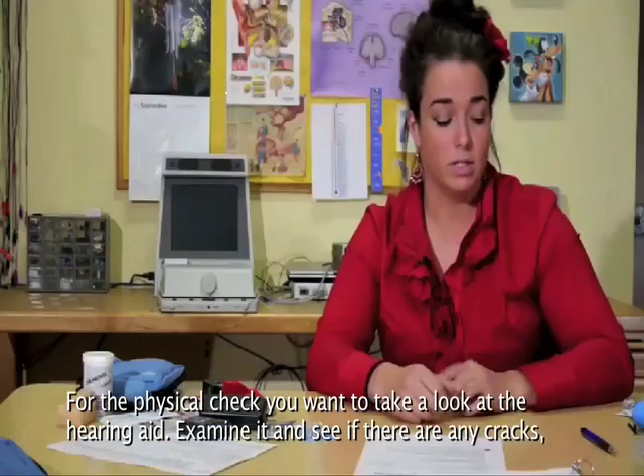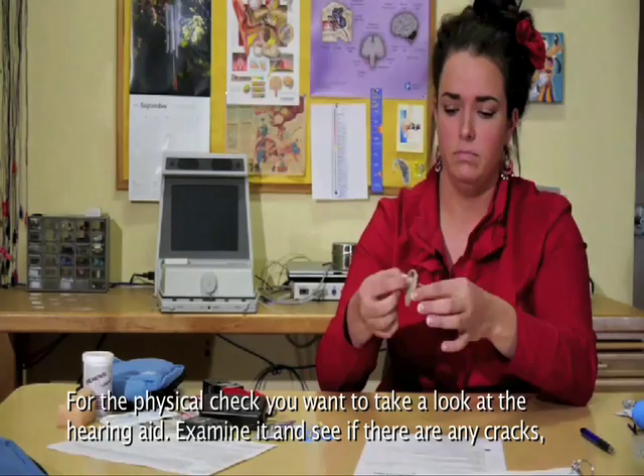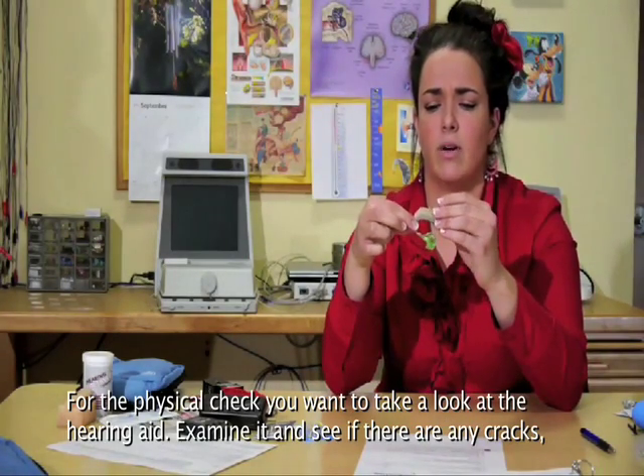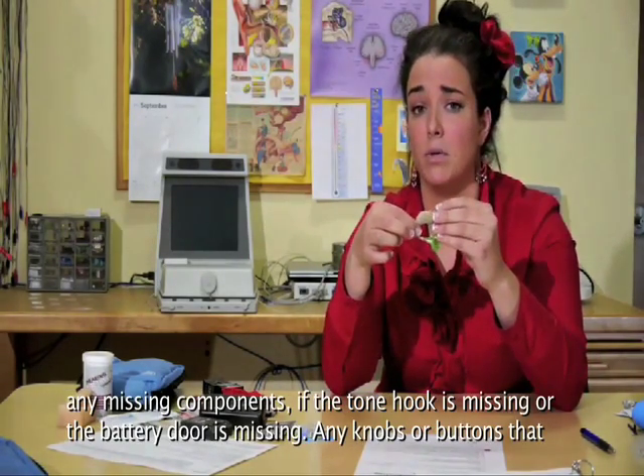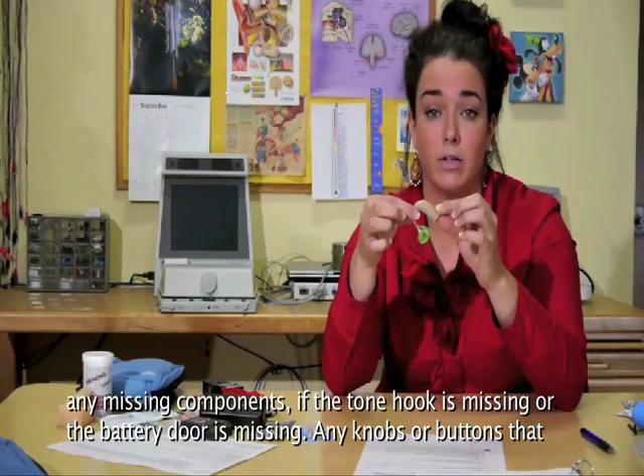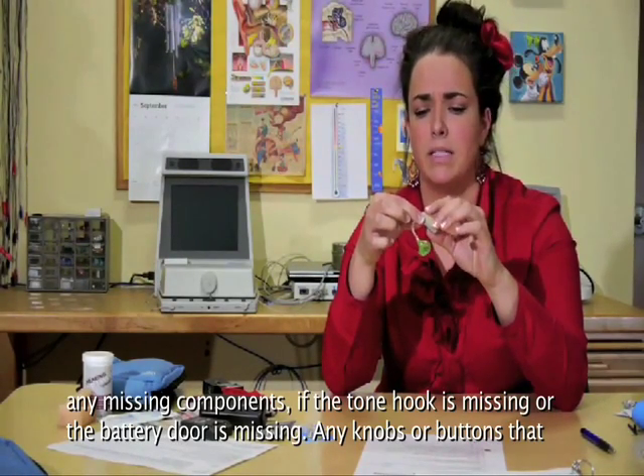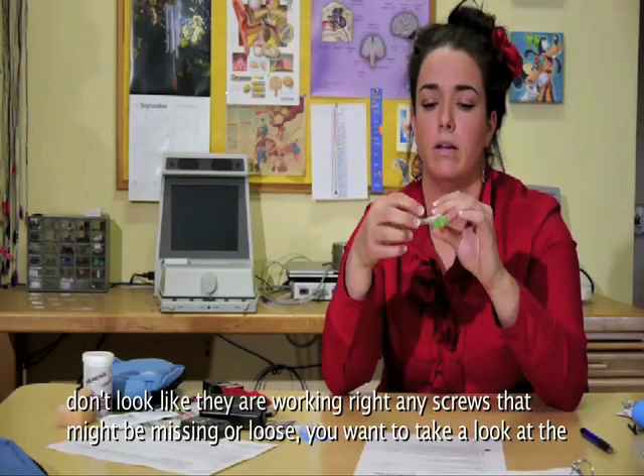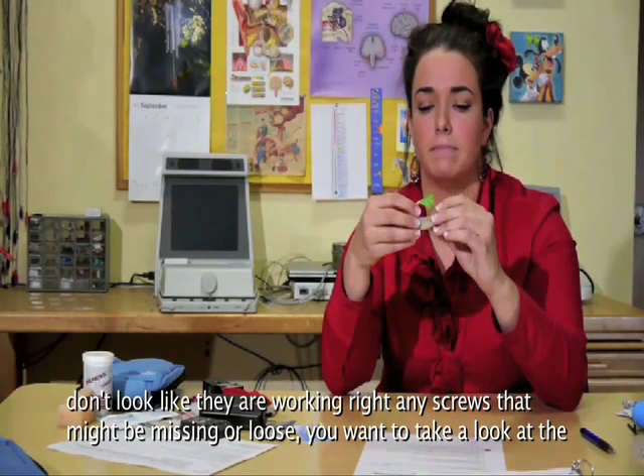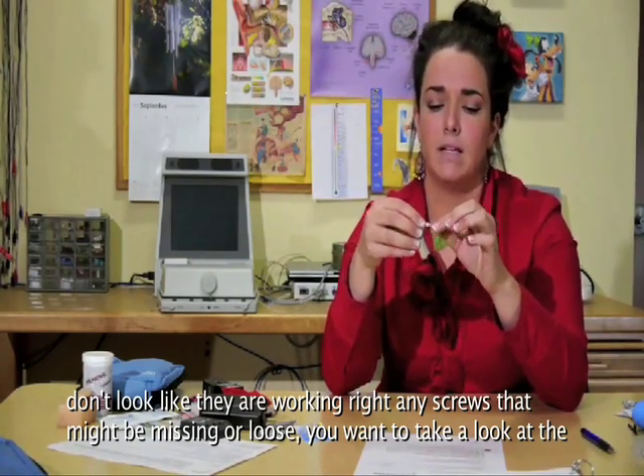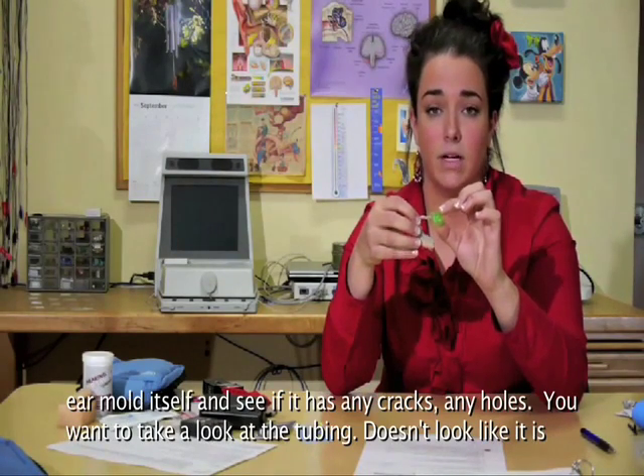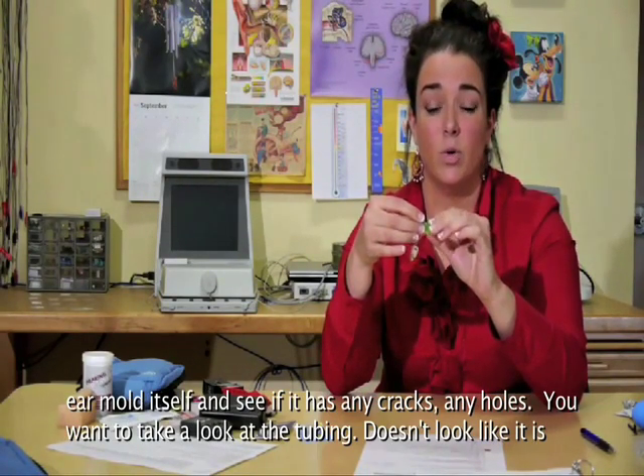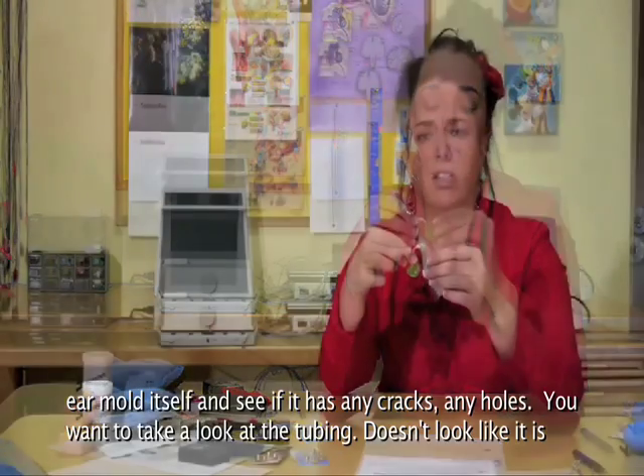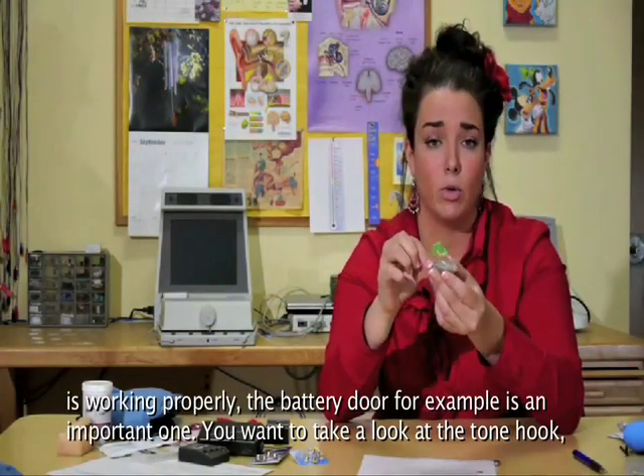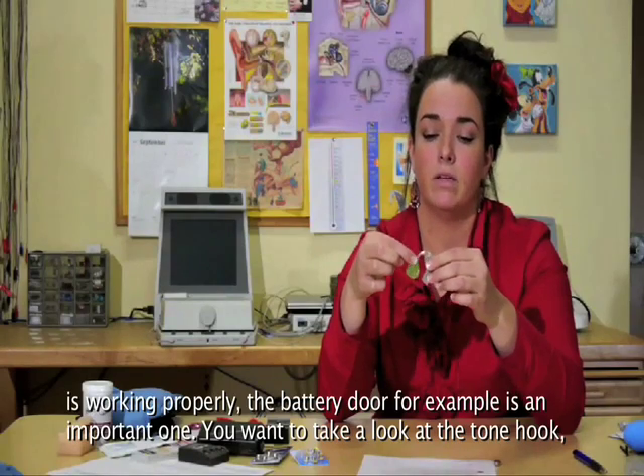For the physical check, you want to take a look at the hearing aid, kind of examine it, see if there's any cracks, any missing components, if the tone hook is missing or the battery door is missing, any knobs or buttons that don't look like they're working right, any screws that might be missing or loose. You want to take a look at the ear mold itself, see if it has any cracks, any holes. You want to take a look at the tubing. Doesn't look like it's working properly. Battery door, for example, is an important one.